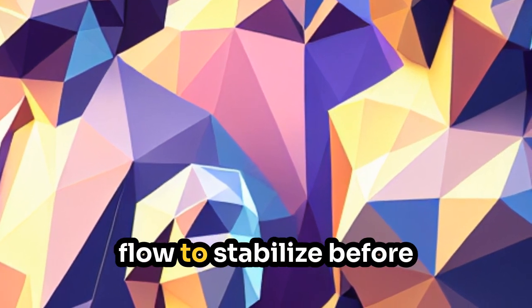Select test points across the meter's operational range, from minimum to maximum flow rates. At each point, allow the flow to stabilize before recording measurements. Compare the meter's readings to a known standard and calculate any deviations.